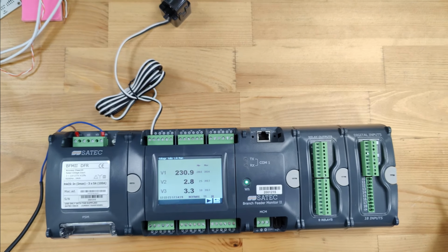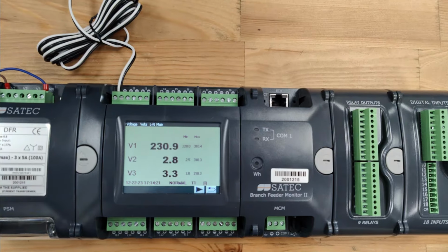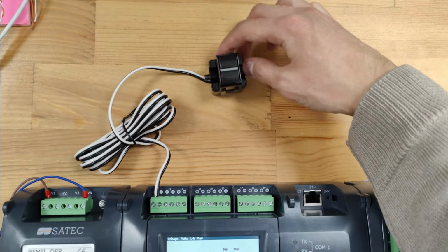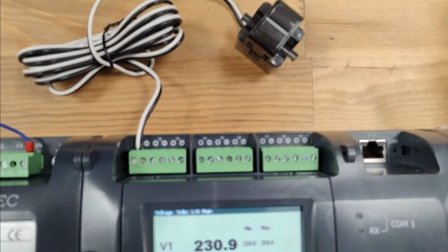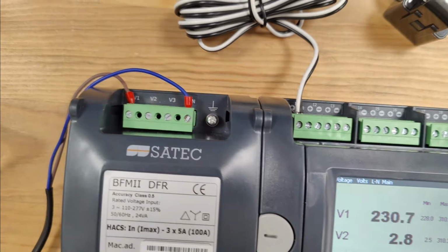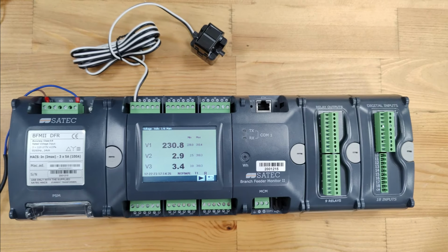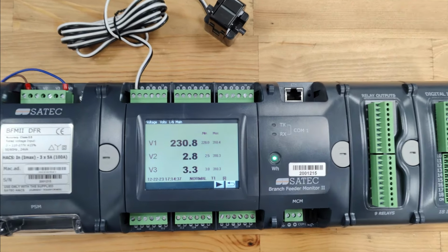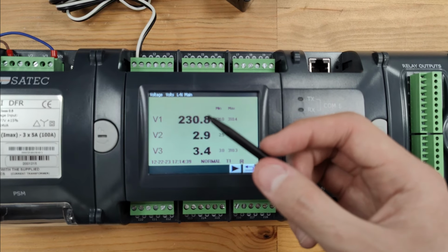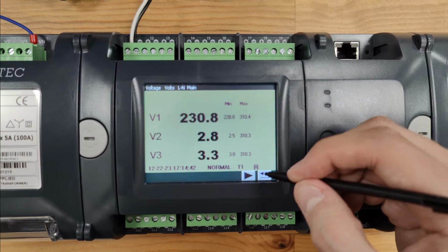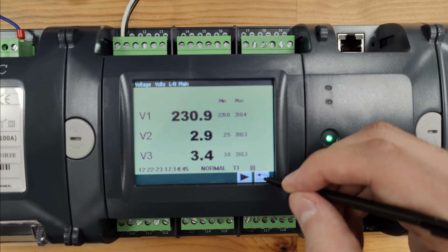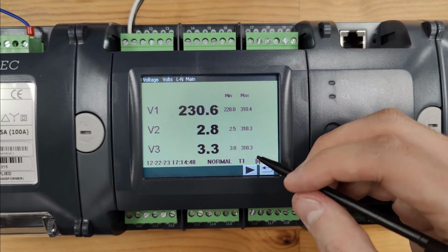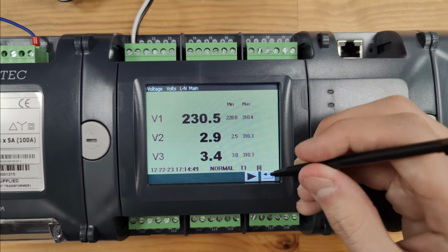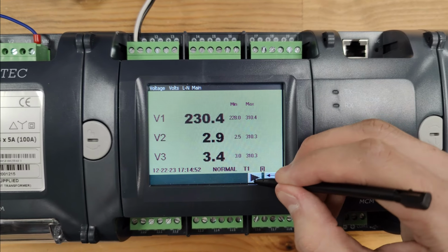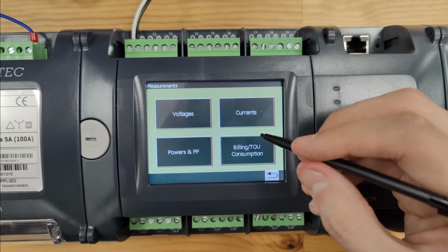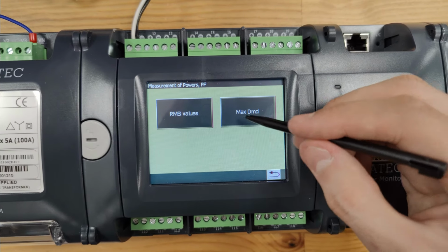Now let's look at how to work with the display of the BFM II device. I connected the transformer for the current inputs. Here you go, for the first current input and voltage input. That is also a power supply module too. And when we turn on the device, I am going to go to another menu of the BFM II. And when we turn on the device, we will see the voltage measurements.